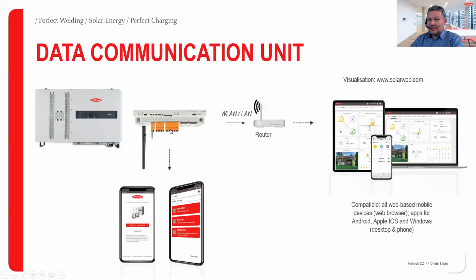On this slide, we can see the data communication unit, which we internally call Pilot. This unit is integrated in every Tauro or Tauro Eco inverter, and it is the main communication component in the inverter. On this card, we have Modbus communication, a LAN port for connection to a router, and Wi-Fi is also possible for connection to a router. Using Wi-Fi or LAN, we also do the initial setting of the inverter. Later we will speak about it in more detail.